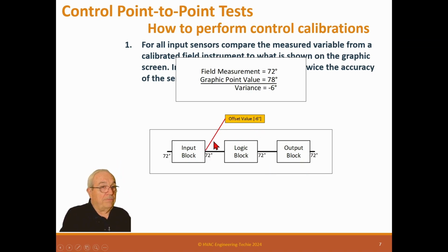Now, you can put this other places, like I've seen them put it here or here. And you don't want to do that because this logic block may be sending that data to other functions. So it may take this 72 degrees, or 75 degrees, or 78 degrees and send it to other functions. So those functions won't work correctly. So we want to always modify just the input block.